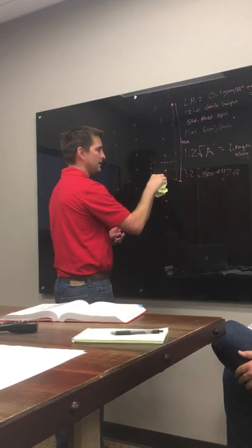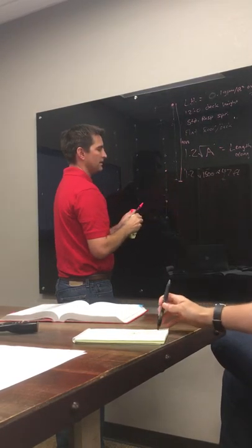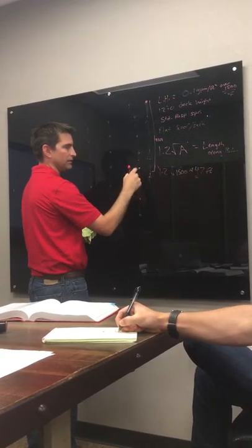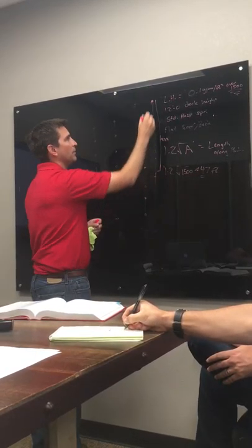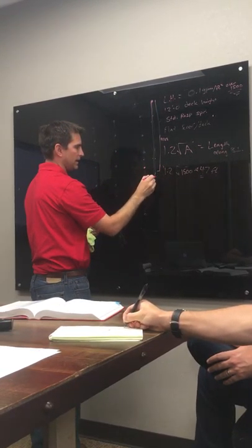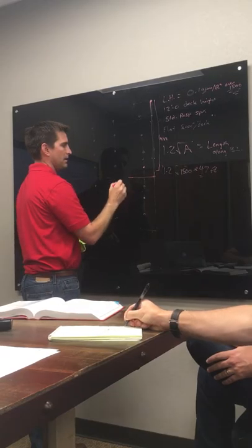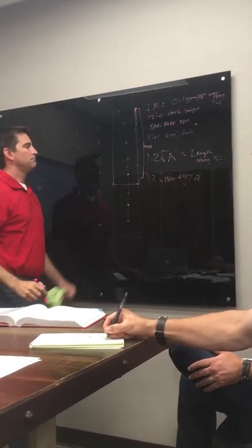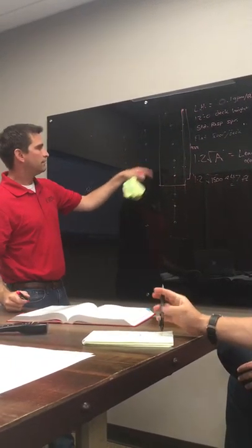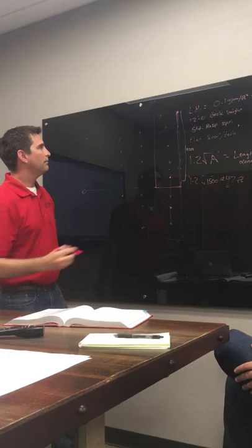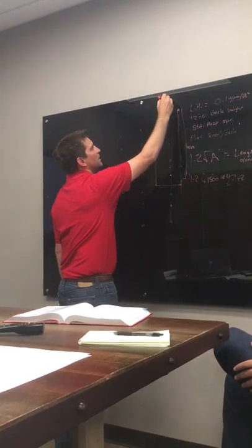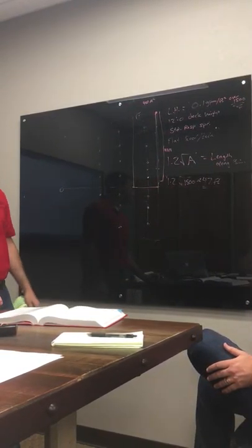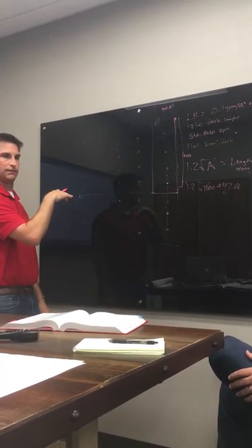All right, so we got our 47 feet, so let me get this out of the way. Let's say we're back to where we were, and 47 fell just short of the halfway point between these two sprinklers. So I really am going to pick up that one. I'd bring my remote area down to the halfway and cut across, and then go halfway between these sprinklers and maybe bring it back up. So that's a rectangle, right? Four sprinklers, rectangle, everything's right. But now we look and that area may only be 400 square feet. Well, you have to have 1500, right?